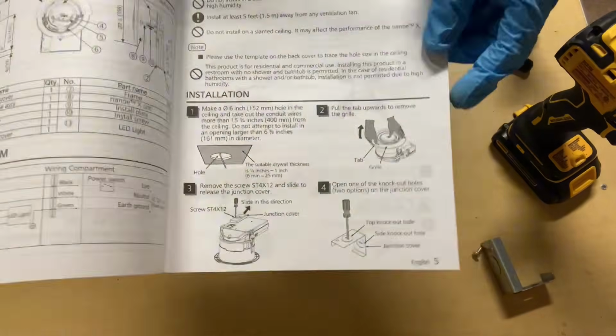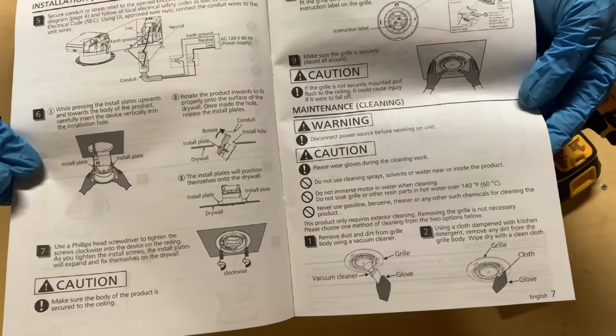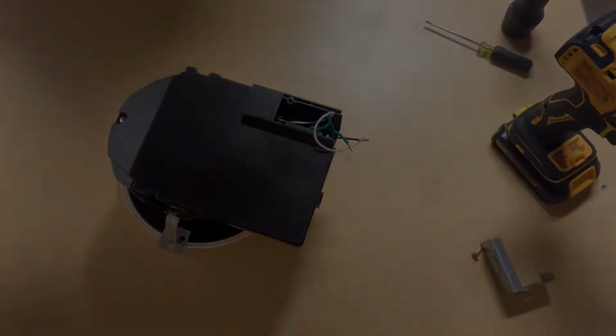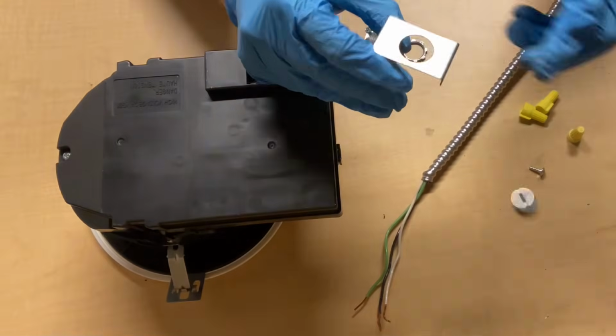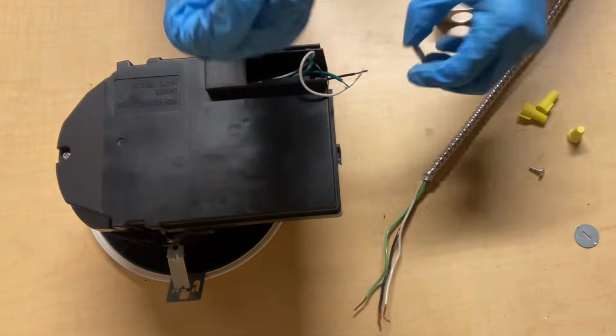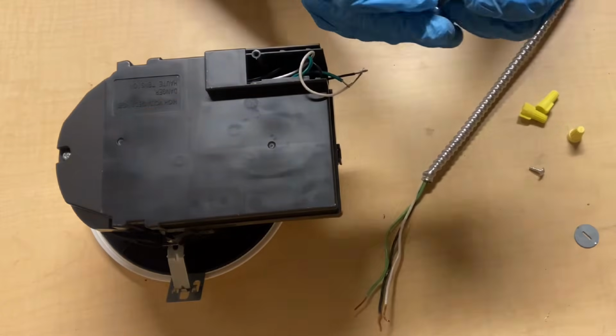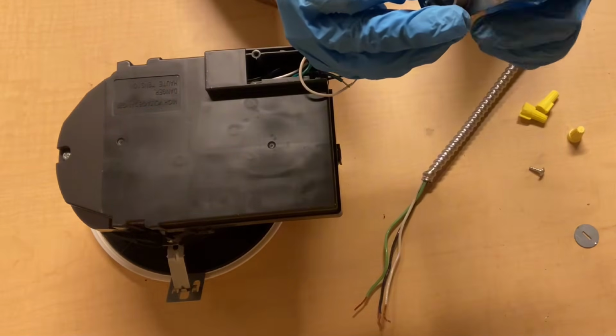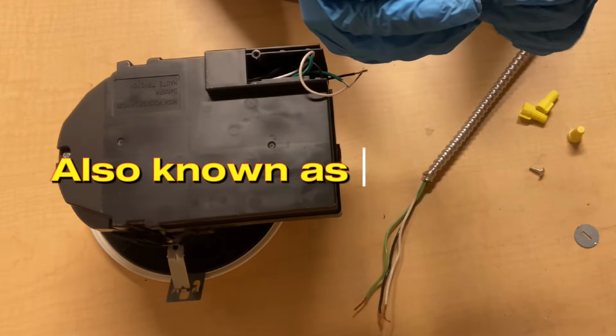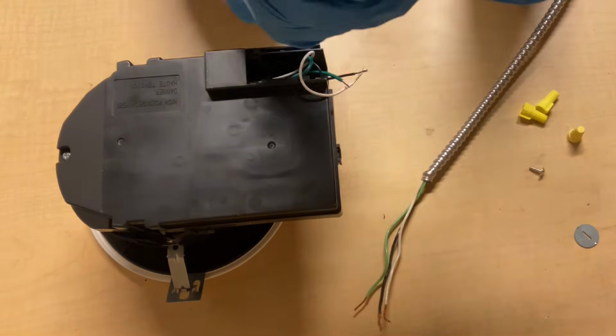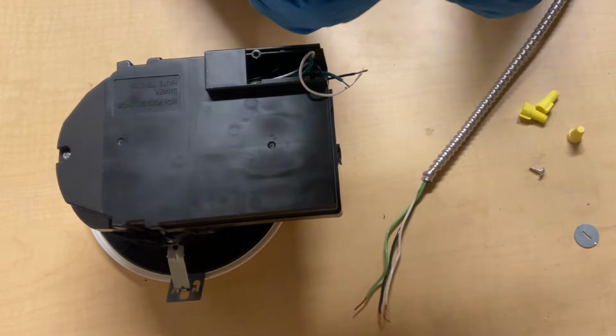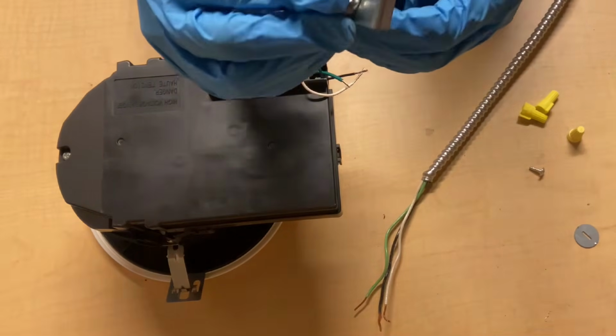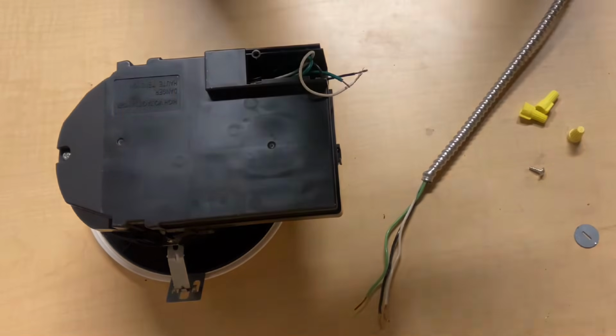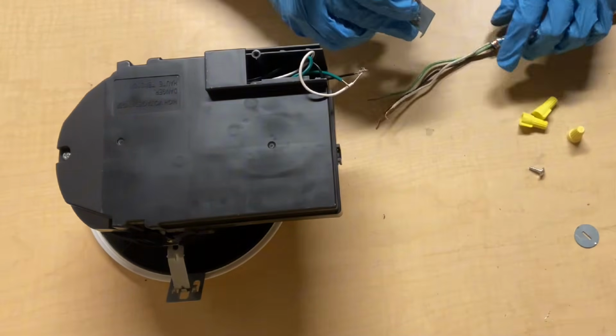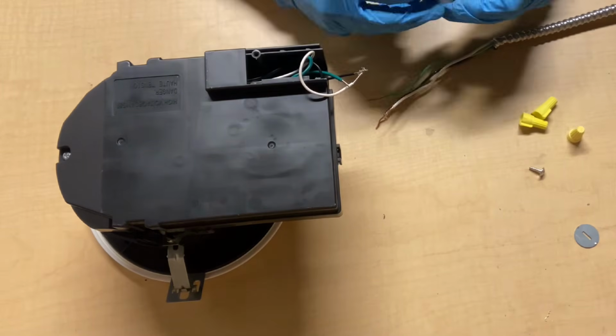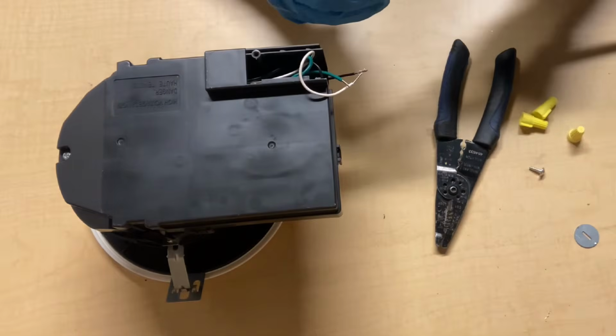And it comes with the instruction book, tells you how to install it, how to wire it. Even comes with a little template so you can cut out your 6-inch diameter circular hole. So I'm just going to punch out that knockout, put in this connector, and you can see I'm using BX cable, which is like a flexible cable. Again, pretty self-explanatory. Your black hot wires, black to black, your white neutral to the white neutral wire, and your green ground wire to the green ground wire.